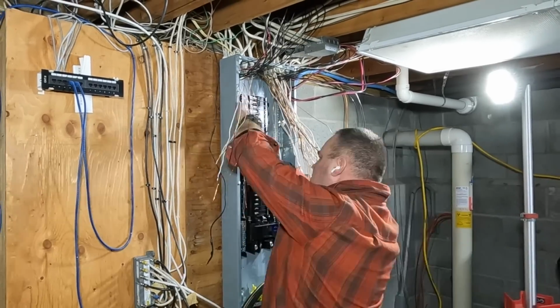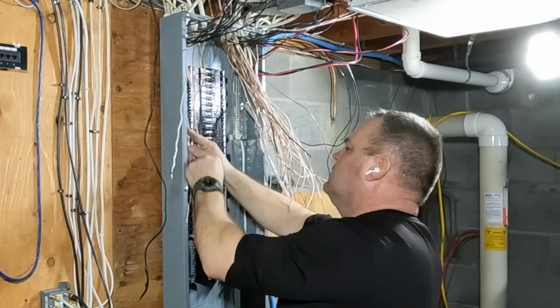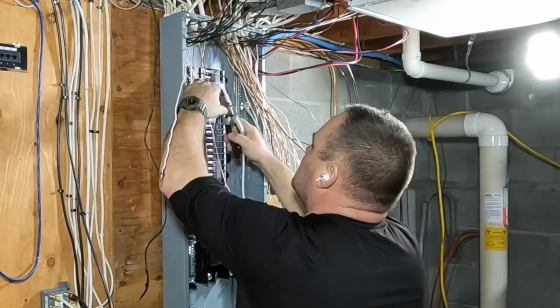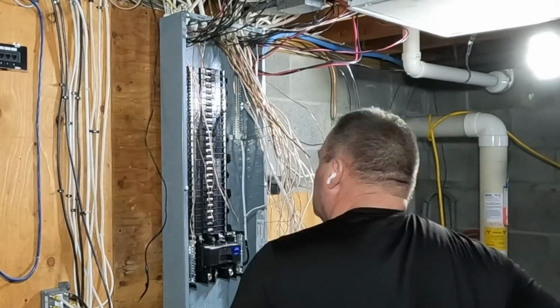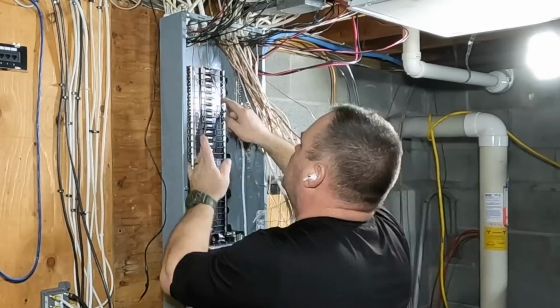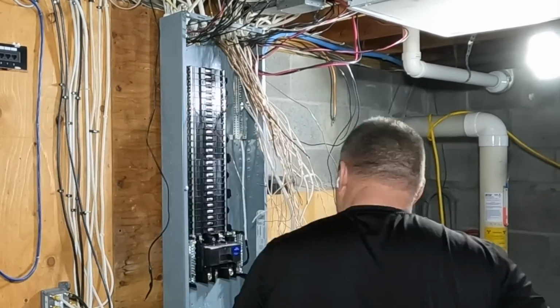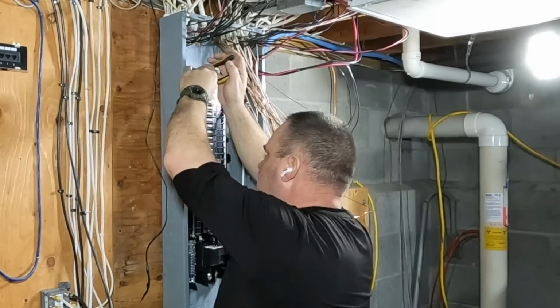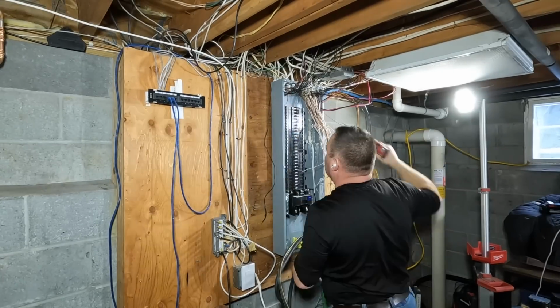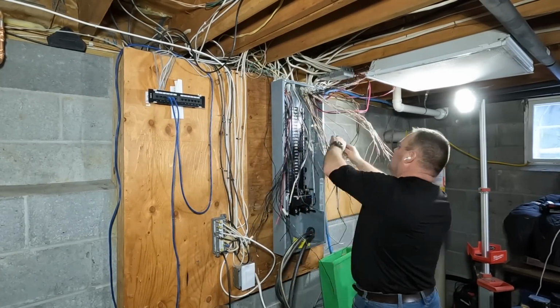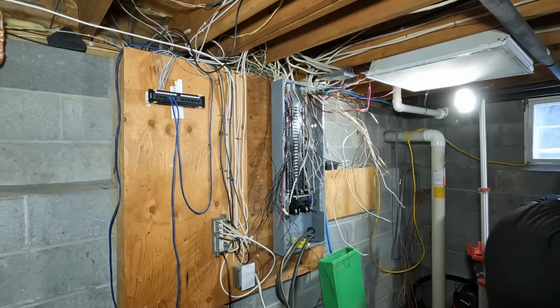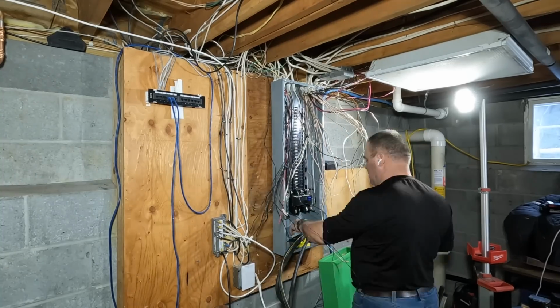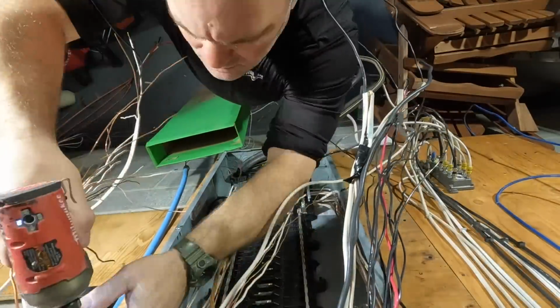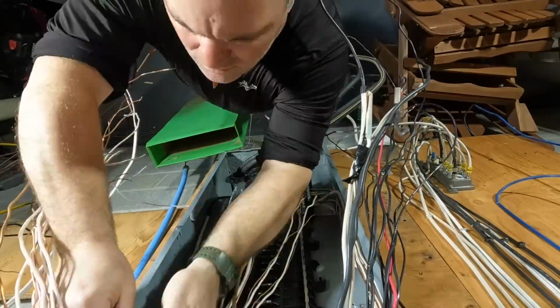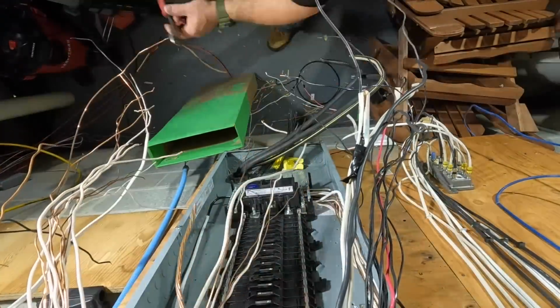Normally non-current carrying conductive materials enclosing electrical conductors or equipment or forming part of such equipment shall be connected to earth so as to limit the voltage to ground on these materials. A3, bonding of electrical equipment. Normally non-current carrying conductive materials enclosing electrical conductors or equipment or forming a part of such equipment shall be connected together and to the electrical supply source in a manner that establishes an effective ground fault current path. A4, bonding of electrically conductive materials and other equipment. Normally non-current carrying electrically conductive materials that are likely to become energized shall be connected together and to the electrical supply source in a manner that establishes an effective ground fault current path. A5, effective ground fault current path.